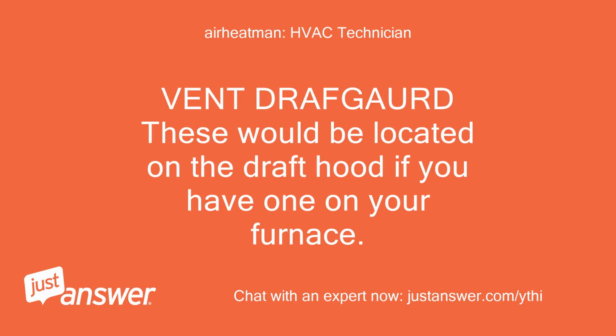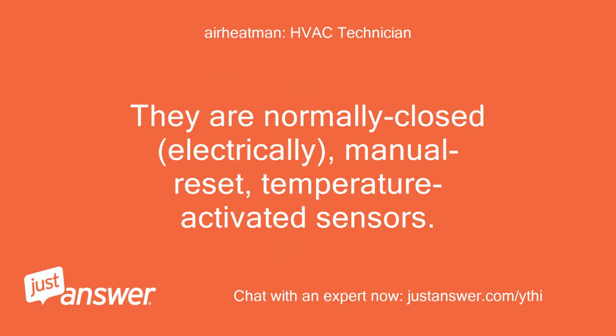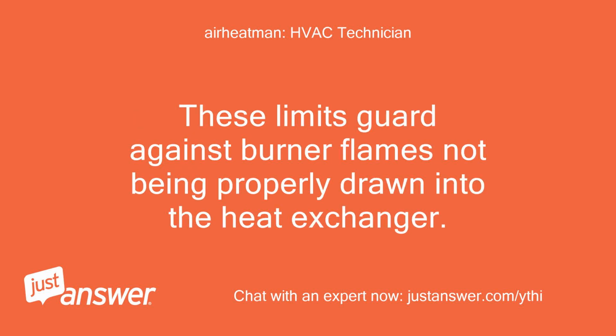Vent draft guard. These would be located on the draft hood if you have one on your furnace. Rollout limit. The rollout limit controls are mounted on the burner/manifold assembly and monitor the burner flame. They are normally closed, electrically, manual reset, temperature activated sensors. These limits guard against burner flames not being properly drawn into the heat exchanger.